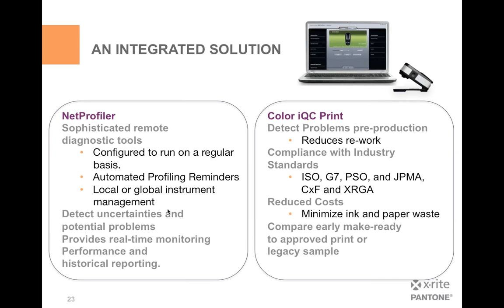Net Profiler is software that will allow you to ensure that, if you have multiple sites or locations, all of the devices that you're using in your network are actually calibrated to the manufacturer's spec. That's done through the net, or the internet. So it's an ability for you to use the software and make sure that your devices are in line, and be able to have the reporting on that as well.